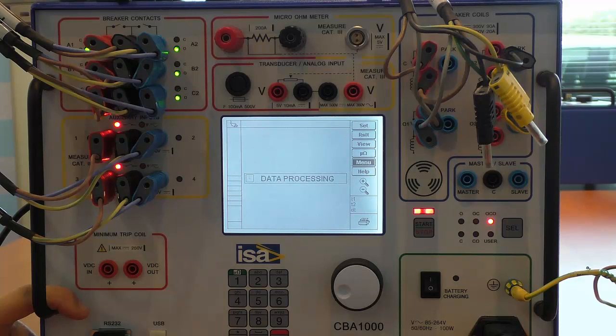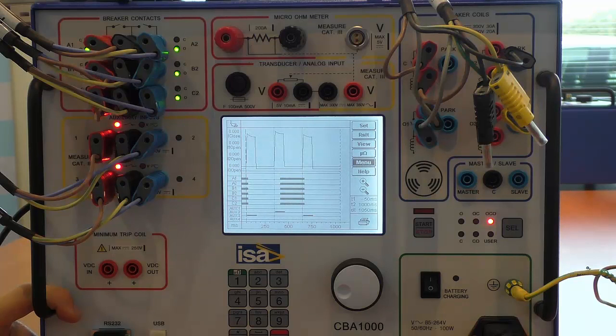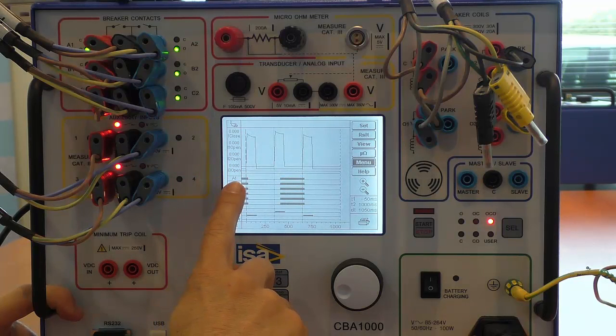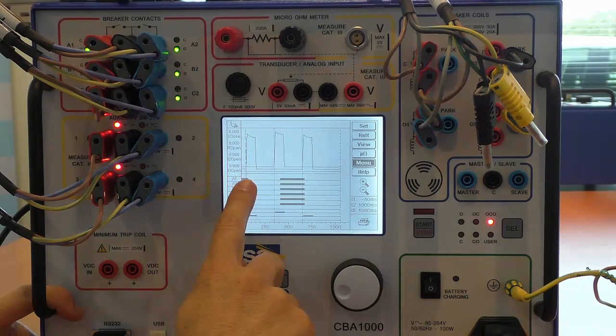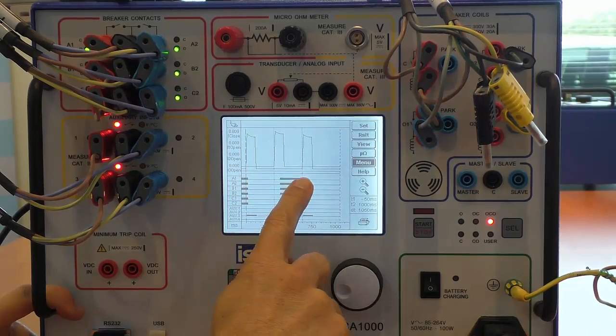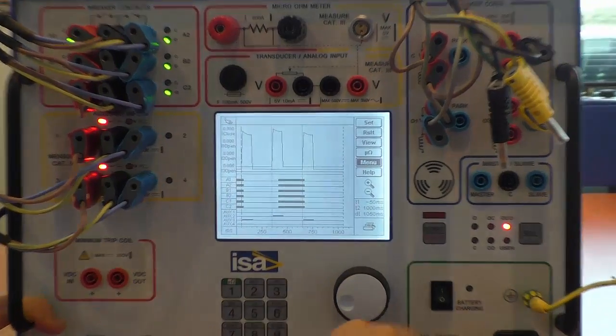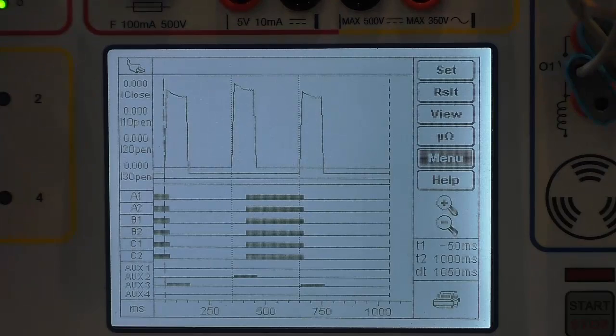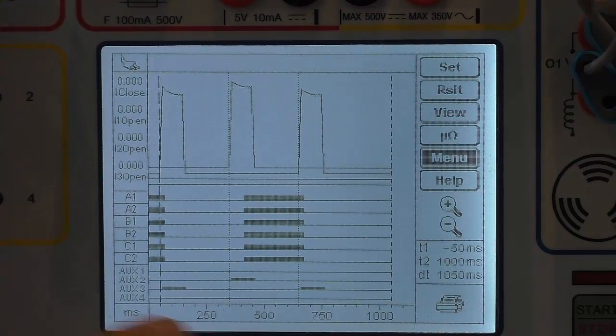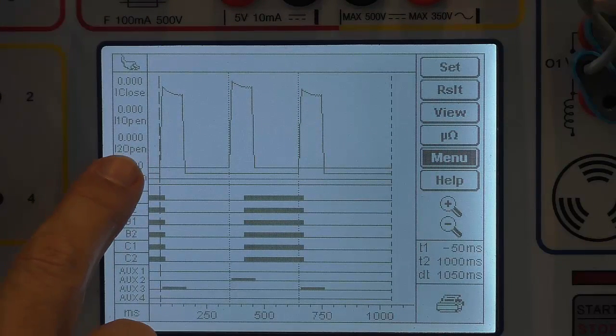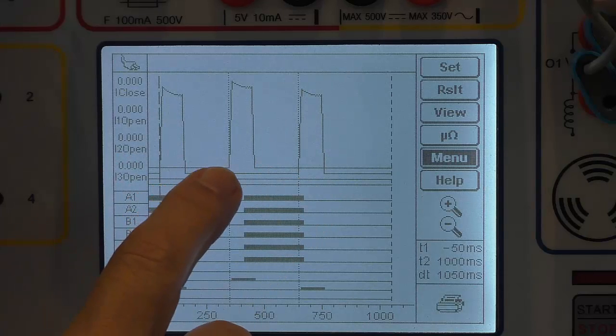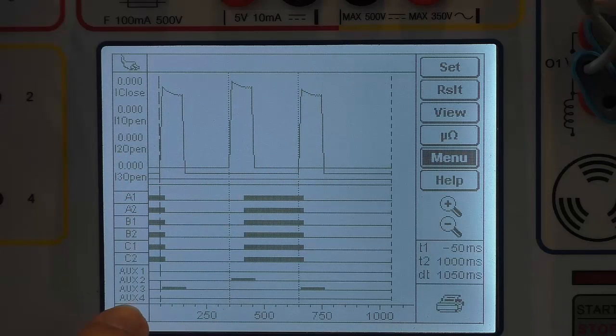Once the operation is complete, you will see the display on the screen, and we can see on the main contacts the transition from close to open, back to close, back to open again, as selected on the open, close, open operation. In this case we can see the intervention of the open coil twice and the close coil once, and the transition of auxiliary contacts as indicated by the bottom trace.